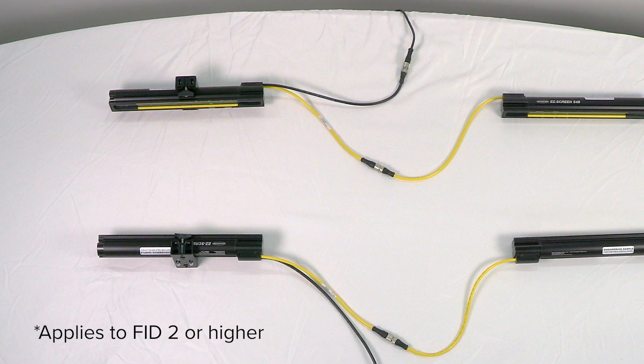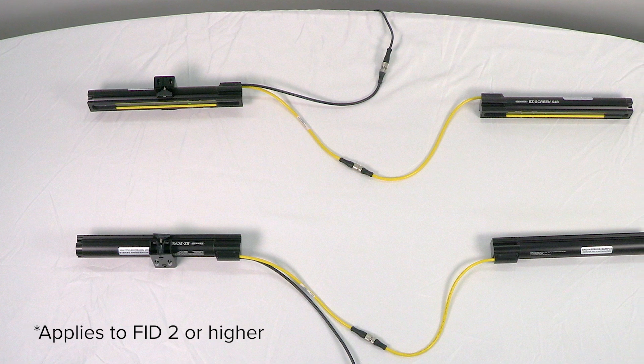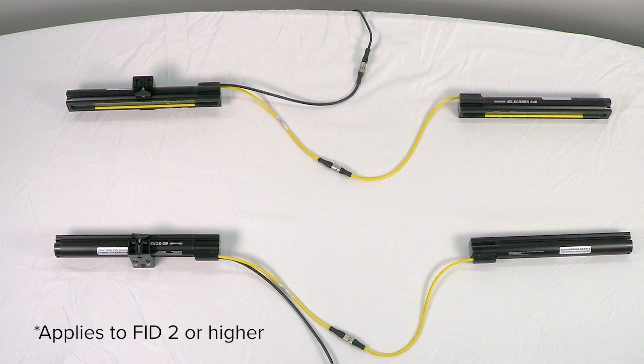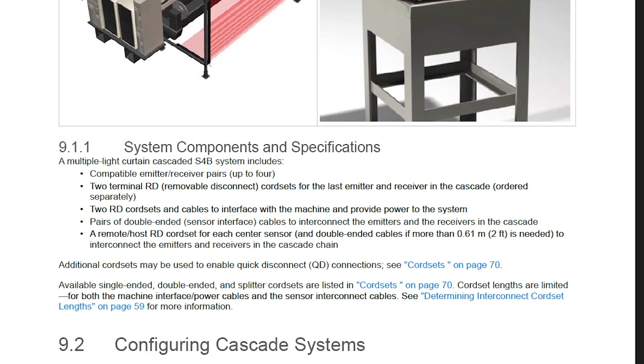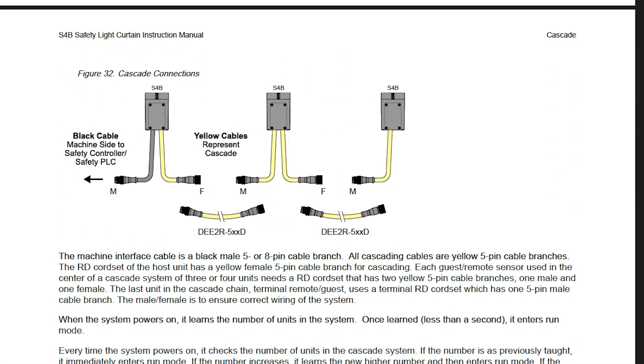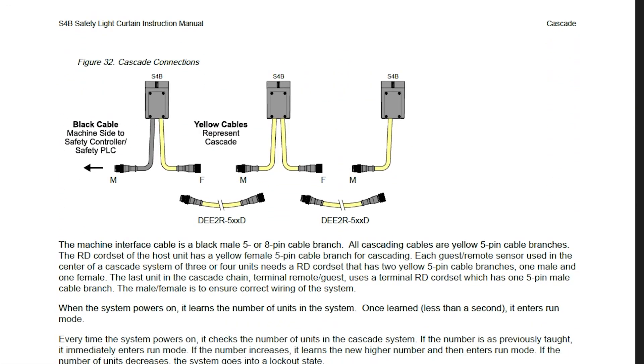All S4B light curtains can be used as standalone units or as part of a cascaded chain with up to four units. Adding multiple curtains to a chain requires the right cord sets, which may be ordered as part of a cascaded light curtain kit.